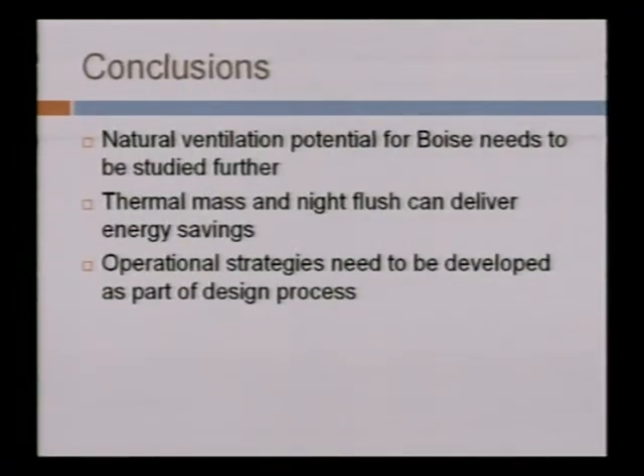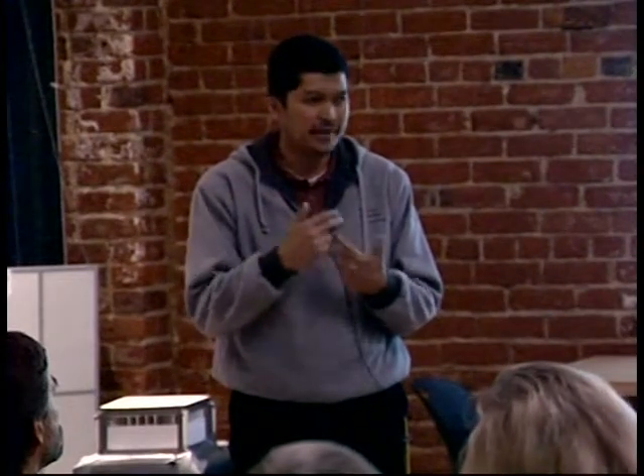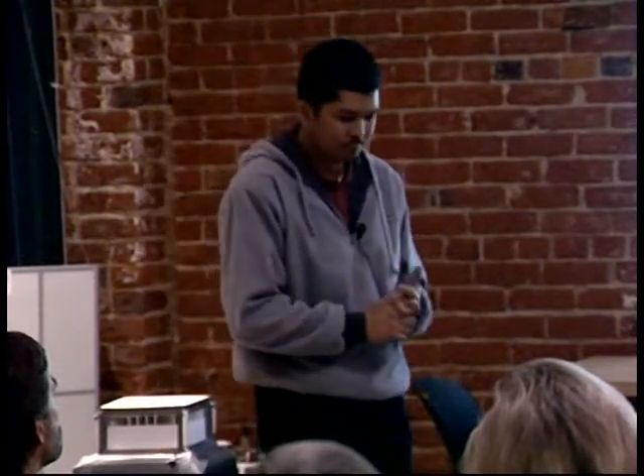And to conclude, natural ventilation potential for Boise needs to be studied further. We know that we have the potential, but we have some hours during the afternoon in the month of June, July, and August where we cannot have free cooling, so that it's not really straightforward natural ventilation cooling that we want to target for Boise, but we want to have a combined strategies: natural ventilation, thermal mass, night flush, even evaporative cooling.